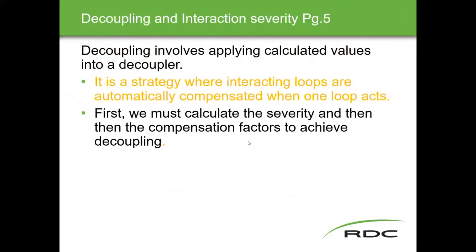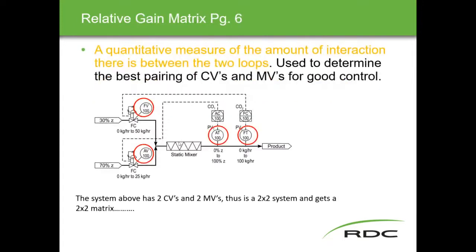Starting out with the calculations — calculating the severity of loop interaction, and from that we get the compensation factors to achieve decoupling. We look at process variables PV1 and PV2, and controlled variables CO1 and CO2. This system has two controlled variables and two manipulated variables, so we call this a two-by-two system, and as a result we get a two-by-two matrix.